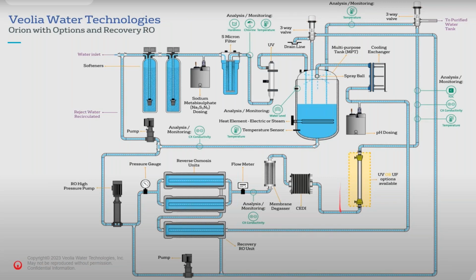And that makes sure that at the end of the points of use, you get the right quality water, consistently. We have the option for a UF membrane. This is a polysulfone hollow fiber membrane, and it has a molecular weight cutoff of 6,000 Daltons. That takes care of any prevailing endotoxins that may be in the system after the CEDI. And so at this point, on the outlet here, you have cold WFI water.